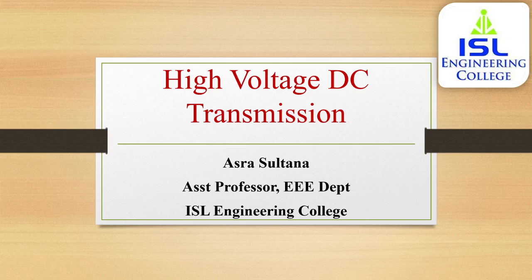Protection against faults in a DC line is invariably through the converter control, mainly due to the non-availability of DC breakers in the early stages of introduction of HVDC systems. However, the reliability of converter control has led to its continued use even when DC breakers have been developed. DC breakers may be required under special operating requirements such as transfer from ground to metallic return and multi-terminal system operation. Corona effects, overvoltages, insulation and protection against faults are some of the aspects that will be discussed here.